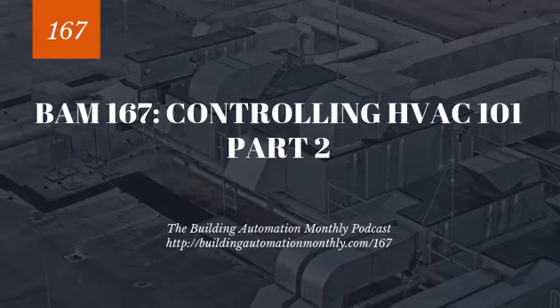By having a 100% outdoor air unit, we can hit our outdoor air requirement and separate those latent and sensible space loads at much lower volumes of air. What I mean by that is if I have to hit 200 CFM outdoor air at the space, I may need to bring in a lot of air on a mixed air unit.